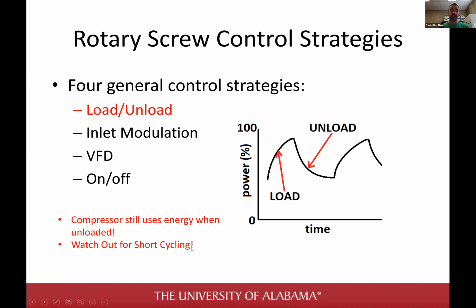Watch out for short cycling. So again, another tidbit, and this will maybe be discussed later in the presentation, but if you do monitor power and you see that this here is not getting down to a flat portion down here, you want this unload portion to get flat at some point in time. And if it's not, it's called short cycling. And that means you're not fully unloaded.